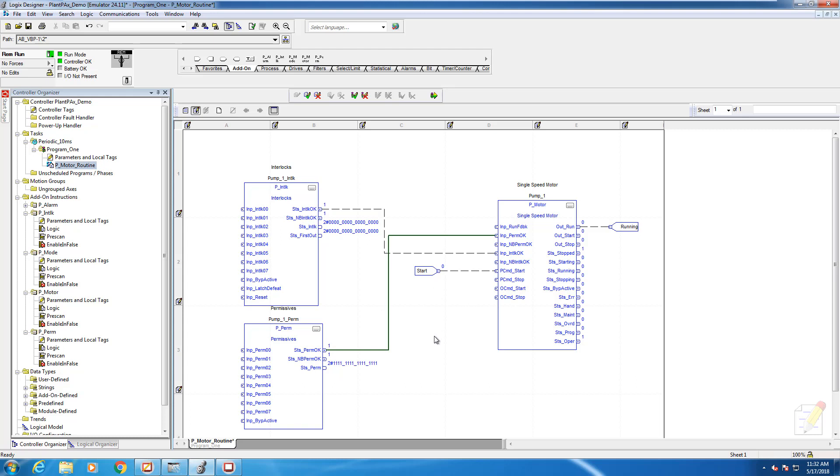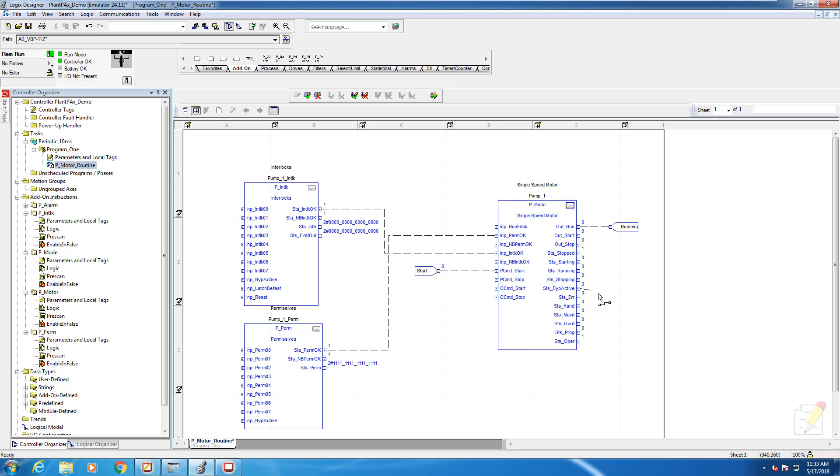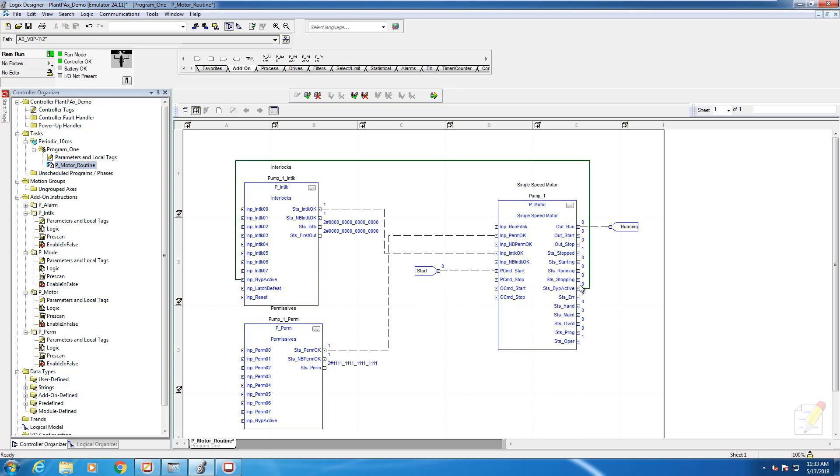The next thing we need to do is wire the status condition of our motor back into the interlock and permissive blocks respectively. We need to wire the status bypass active of the motor block to the input of the permissives and interlocks. Once again, there's a connection point that allows us to do that.